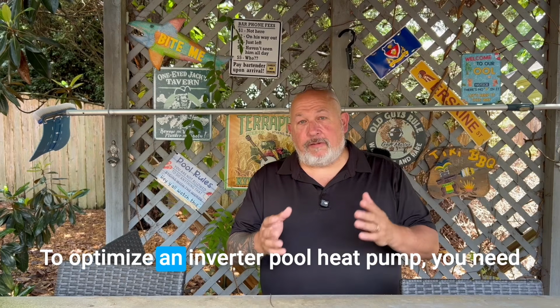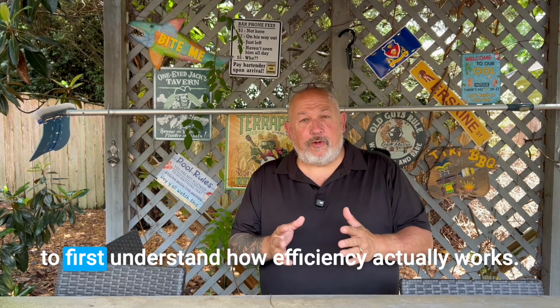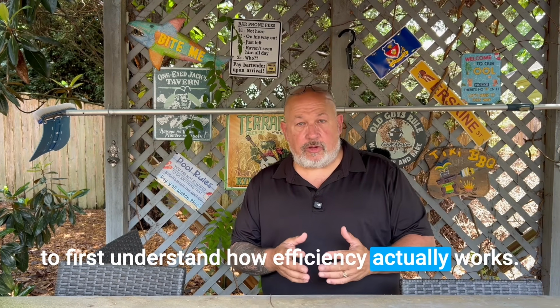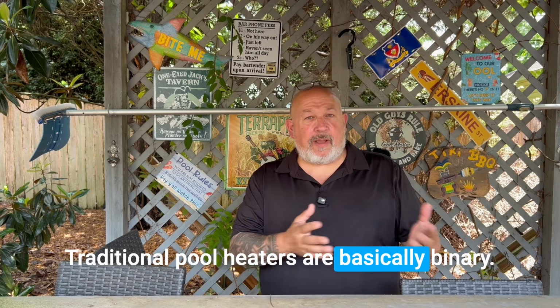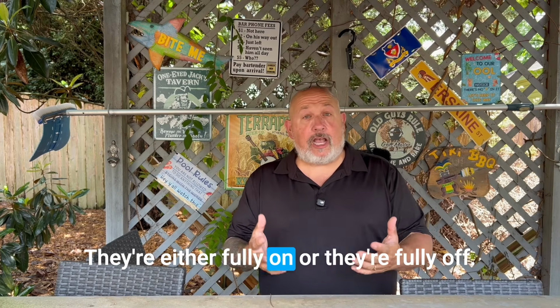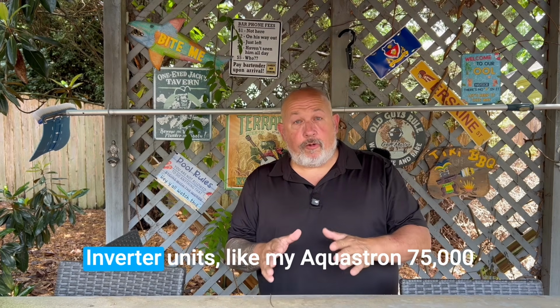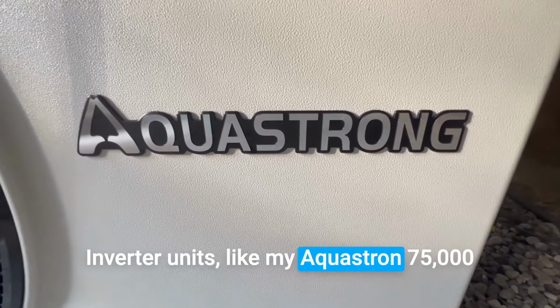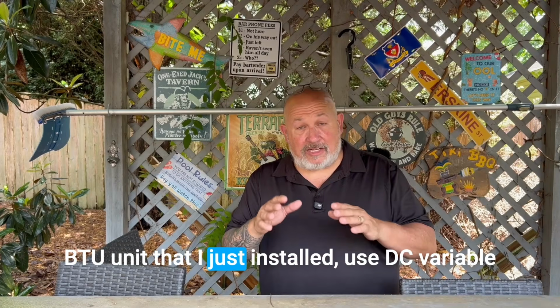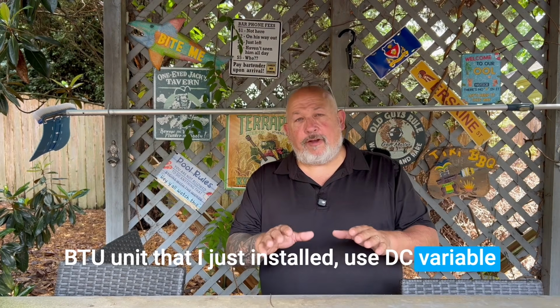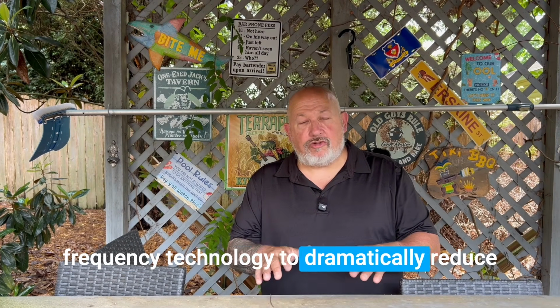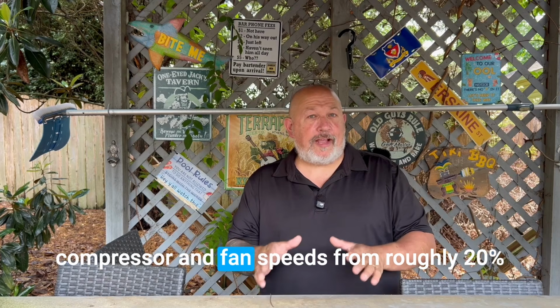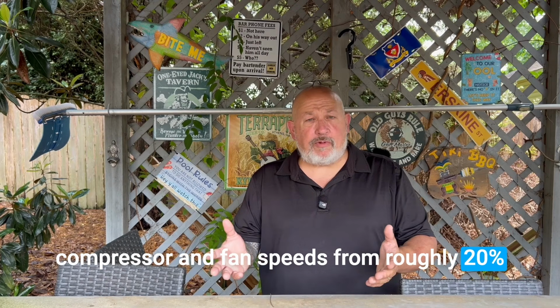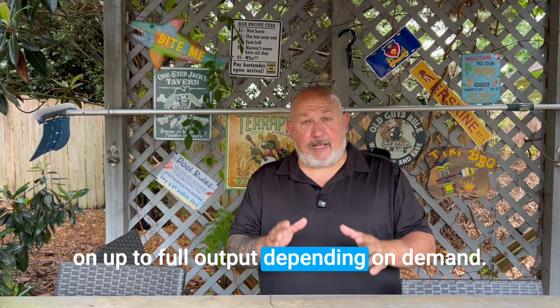To optimize an inverter pool heat pump, you need to first understand how efficiency actually works. Traditional pool heaters are basically binary. They're either fully on or they're fully off. Inverter units, like my Aquastron 75,000 BTU unit that I just installed, use DC variable frequency technology to dramatically reduce compressor and fan speeds from roughly 20% on up to full output depending on demand.